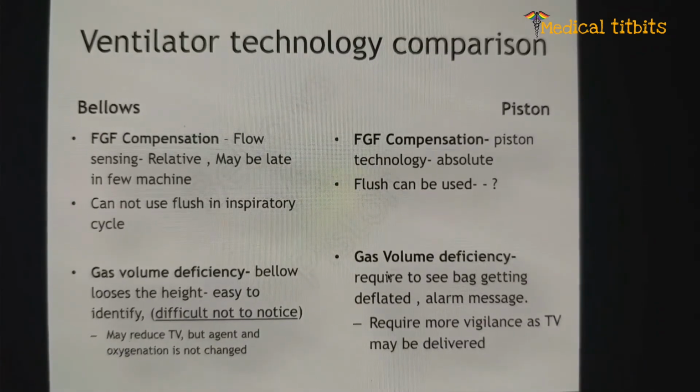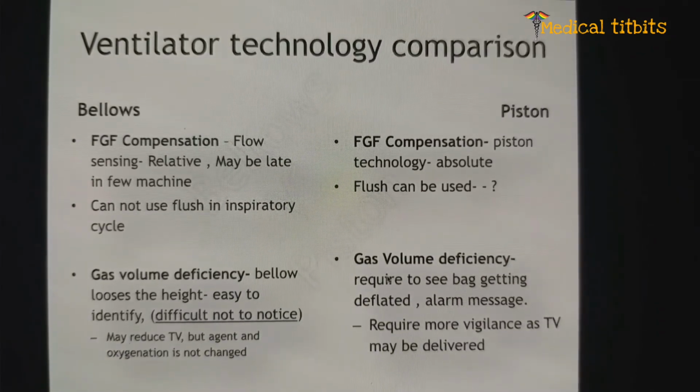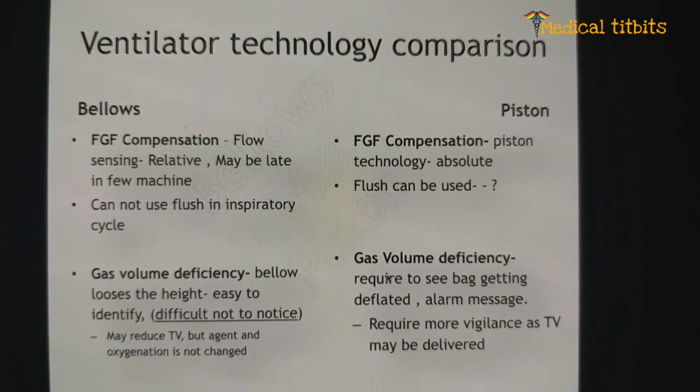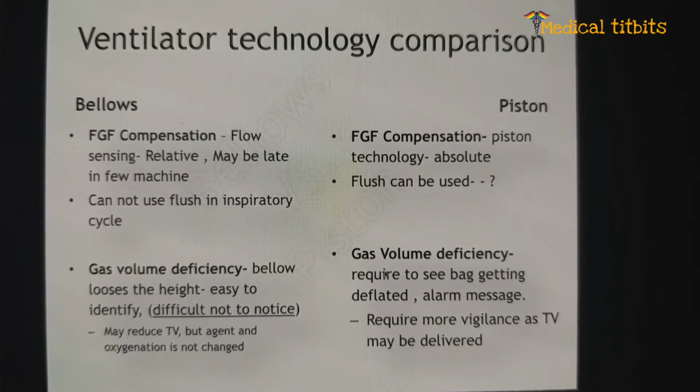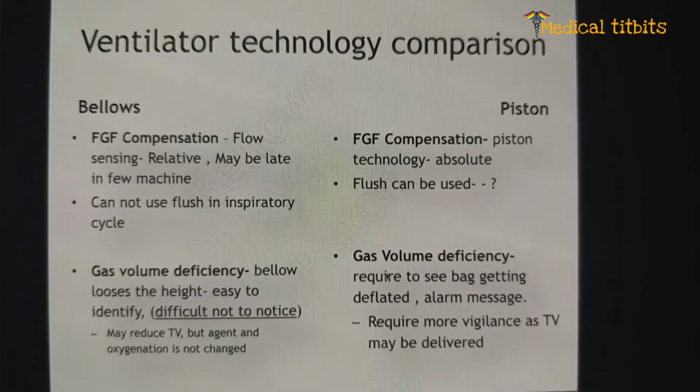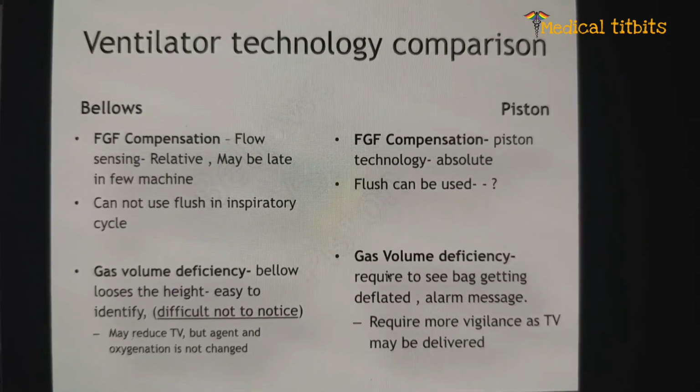Well, in case of piston, the gas volume deficiency will show your bag getting deflated, and you have to really instruct your assistant not to silence the alarm and go ahead, because it can draw air and it can deliver. So you may actually not notice for some period. So it is very important that you should always look at the alarms.